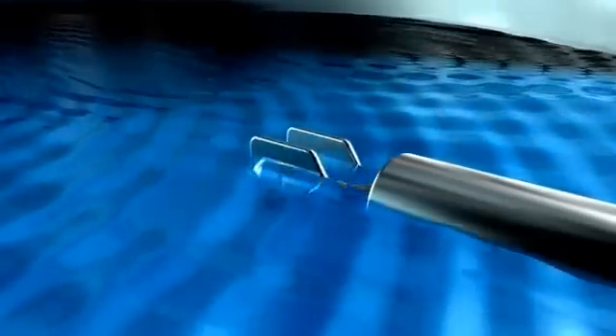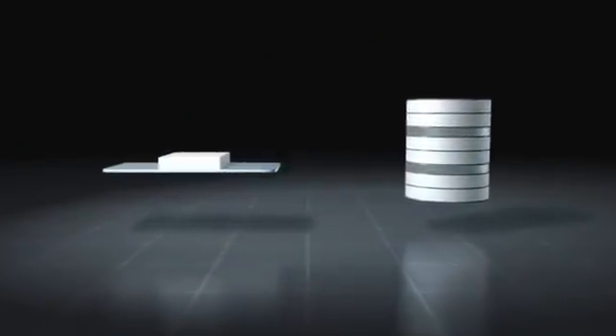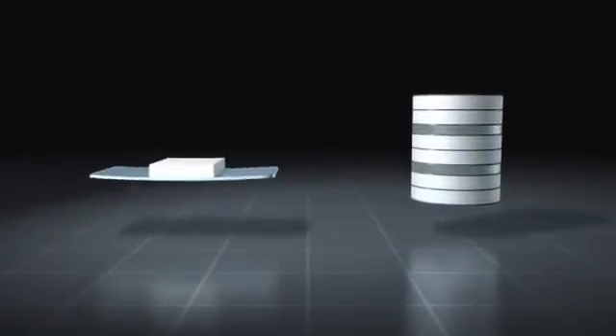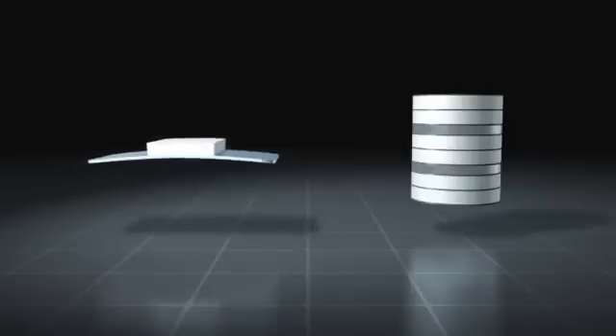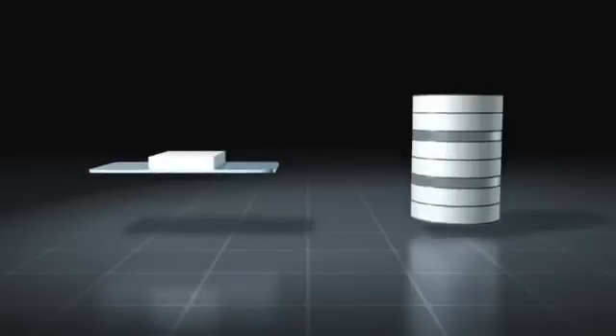The vibronic measuring principle in liquids is based on the resonance shift of a piezo-electrically excited oscillation system. There are two different piezo-electric drives: the bimorph drive in standard instruments and the stack drive in coated instruments.